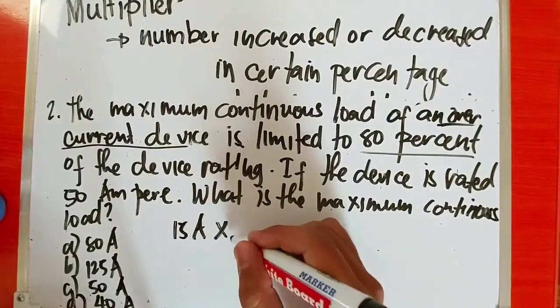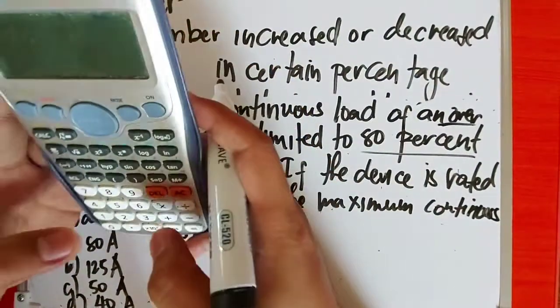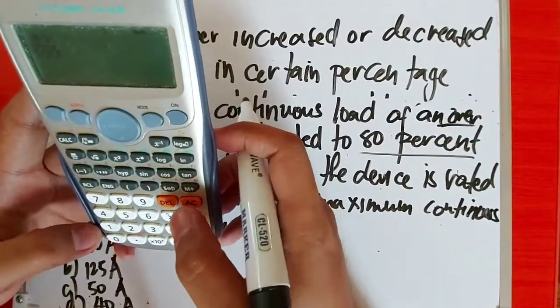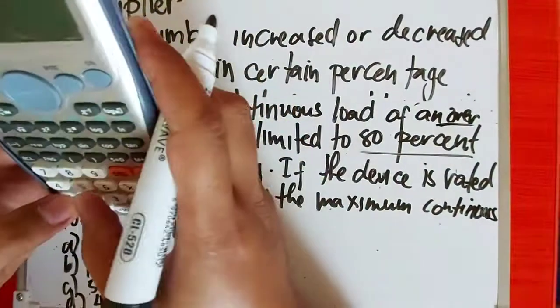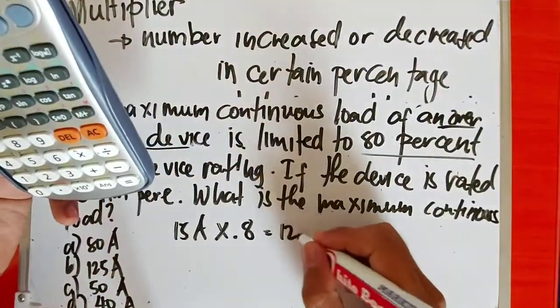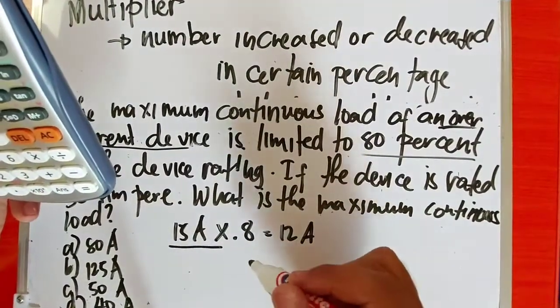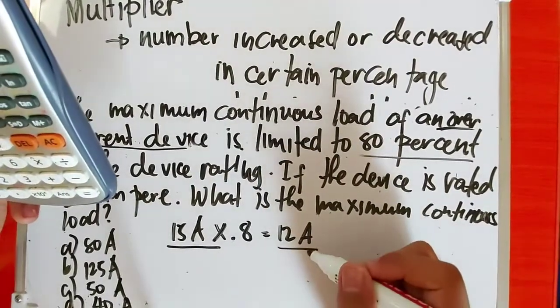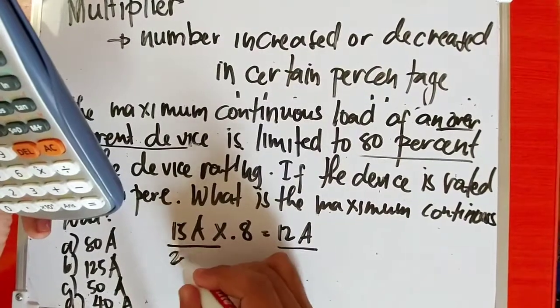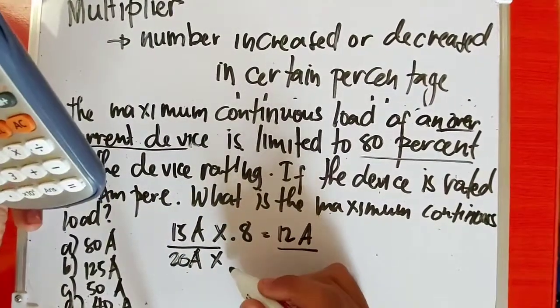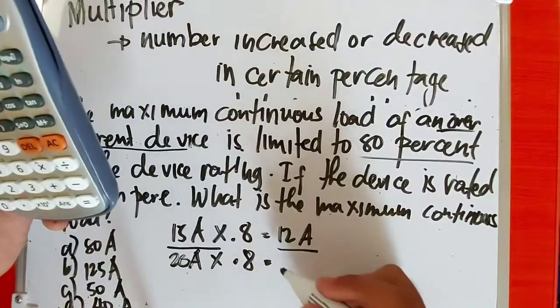Okay, so if your 15 ampere breaker is derated times 80 percent, that's 0.8. Why did it become 0.8? 80 percent converted into decimal is divided by 100, so the answer is 0.8. So that's why we have a 0.8 multiplier. So when you multiply your 15 ampere breaker times 0.8, the answer is 12. So on that circuit breaker of 15 amperes, you can't use 100 percent of its capacity. You'll only use 80 percent of it, which is 12 amperes. This 12 amperes is where you can determine how many lights you can put on it or what load you can connect. For example, if you have a 20 ampere breaker, same thing - when there's an overcurrent protective device, you can't use its full capacity. 20 times 0.8 is 16 amperes only.